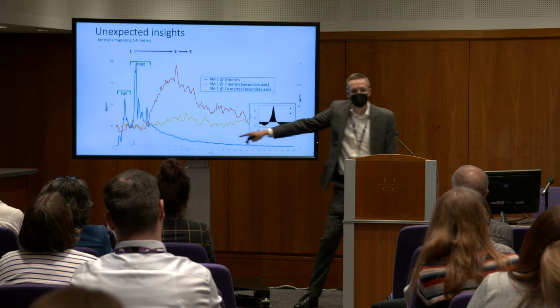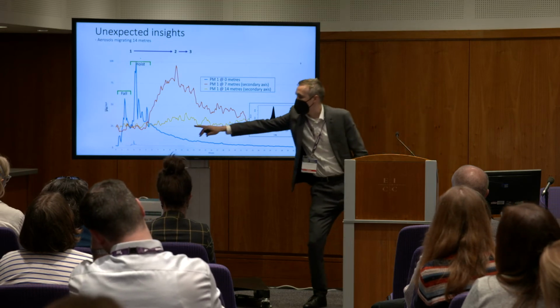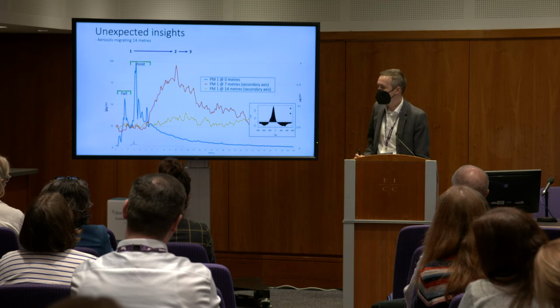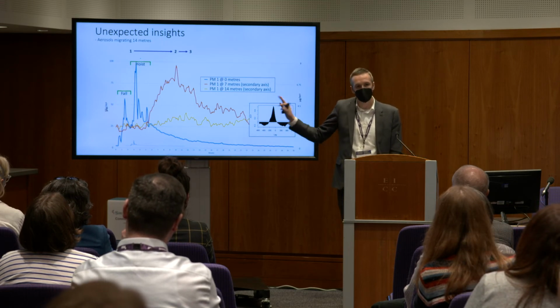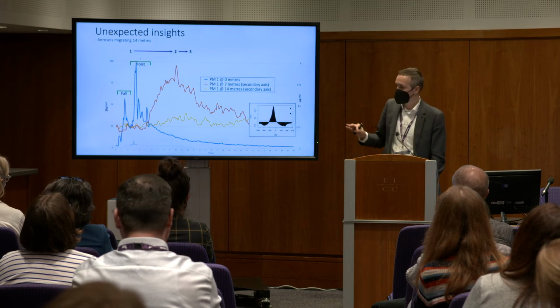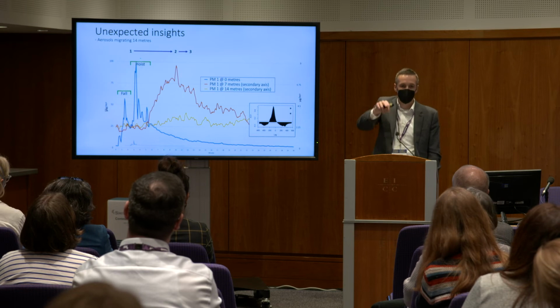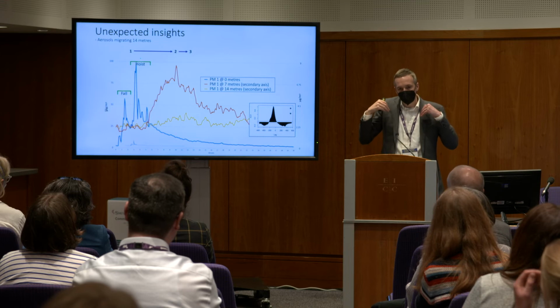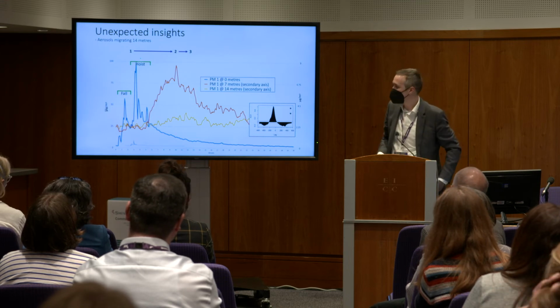It was then detected at sensor 2, which is just outside in the corridor. And then it was detected in sensor 3. And then one of our engineering professors, Professor Clive Beggs, who is really good at looking at time series data, showed that that is correlated. You could see it on the previous slide, that there wasn't anything happening, and then something happens, and then nothing happens. And we saw that with each of these sensors. So it was almost like ripples from a pond. You drop a stone, and then these aerosols are being migrated out.